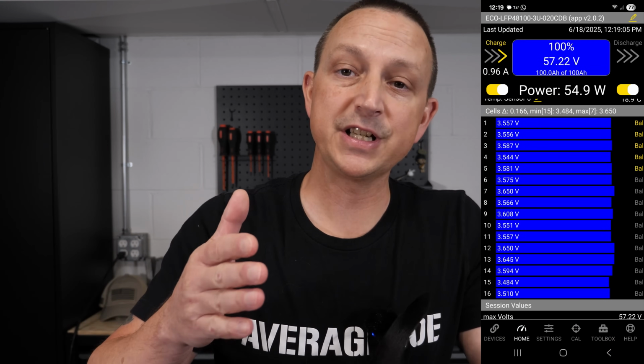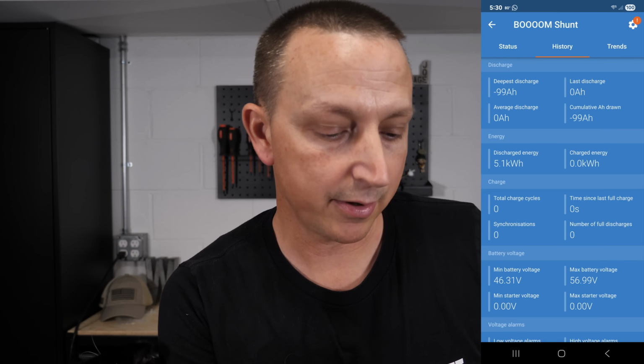Next we'll do the capacity test results, even though you technically just saw them, but I'll explain my process and how it all went down. For the very first battery, I charged it up as high as I could go, right around 57.2 volts. Once it reached that, I used the EG4 Chargeverter to do a 0.2C discharge, or capacity rate test, which ran fine. When we got down to 42 volts, or whenever one of the first cells hit 2.5 volts, the shunt trip breaker flipped the main breaker and the test was over. I got 99 amp hours, or 5.1 kilowatt hours, which is slightly below the advertised 100 amp hours.